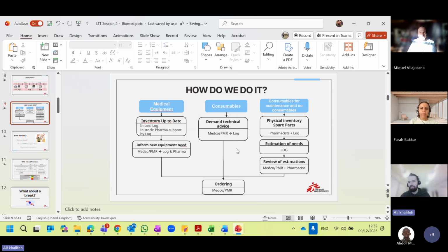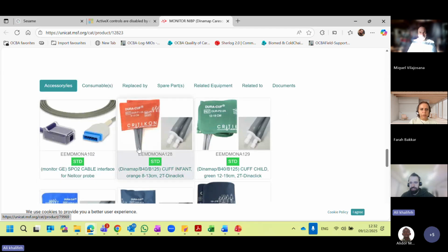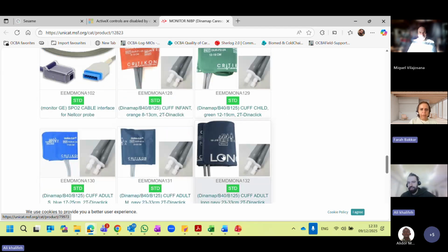So always we need to advise to check with the medical team about the consumables if they are requested or not. For example, this Dinamap, we have a lot of spare parts with it, but a lot of accessories and consumables. These accessories and consumables, they are for medical team. Because they are, for example, the cuff for an NIBP, we are using many time, but we are always in debate, it's medical or logistics, so it's better to do for the monitor, for the concentrator, for all the equipment to check with medical team if the consumables are requested or not.